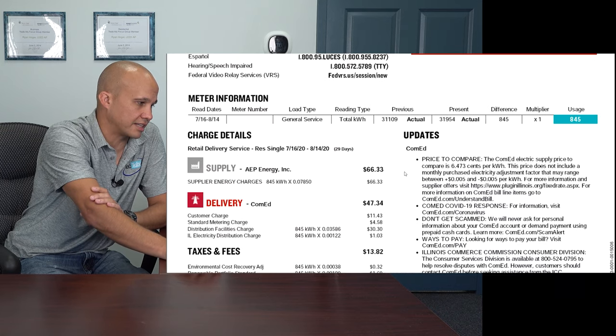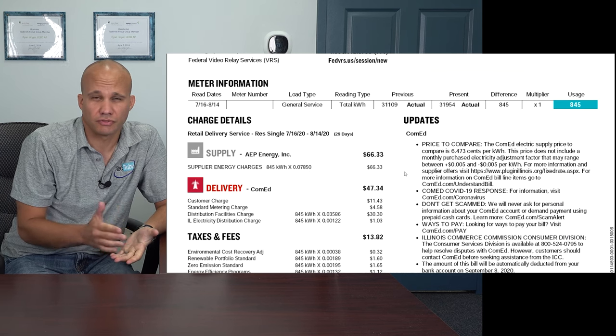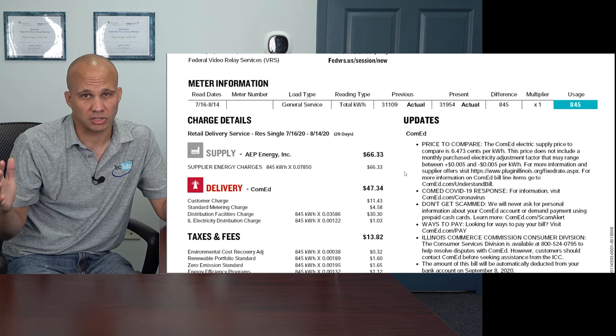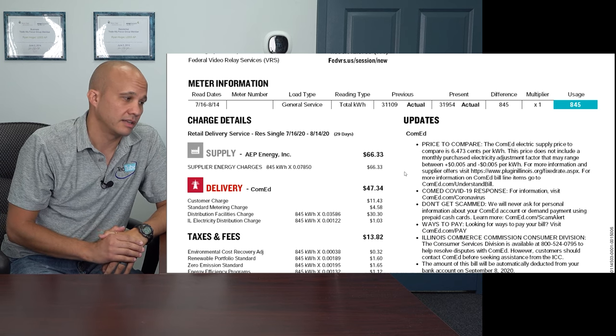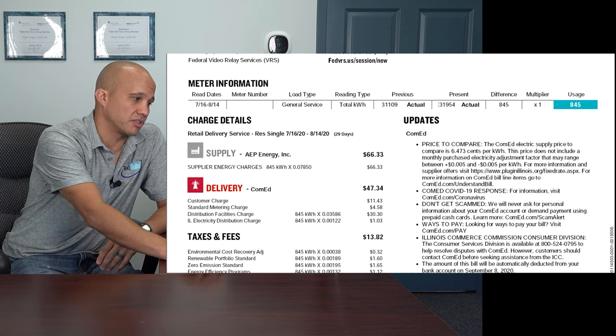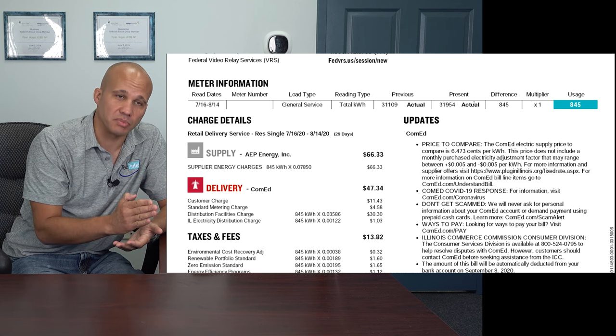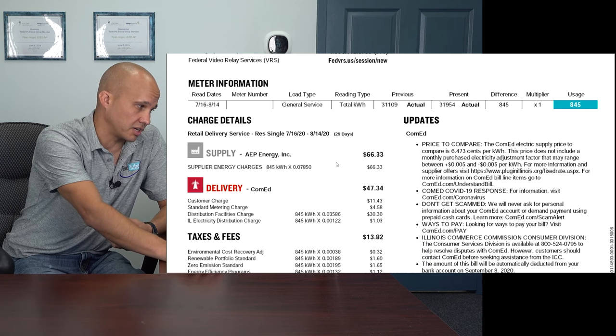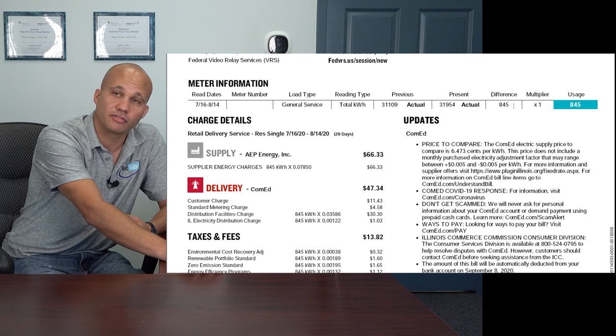When you scroll down and look at the breakdown of the bill for energy calculations, you want more than one month — look at multiple months so that if there's an anomaly you don't get thrown off. You also want to make sure the bills say 'actual' for the meter read. If they're estimated, that's just a guess based on previous years. You want actual meter readings. In this case, it shows you the dates, how much KWH you used on each meter reading, and the difference — 845 KWH is what you're actually paying on.